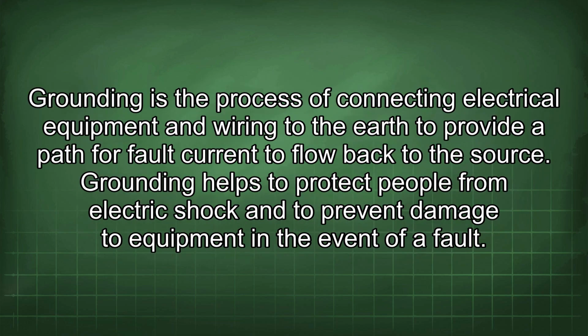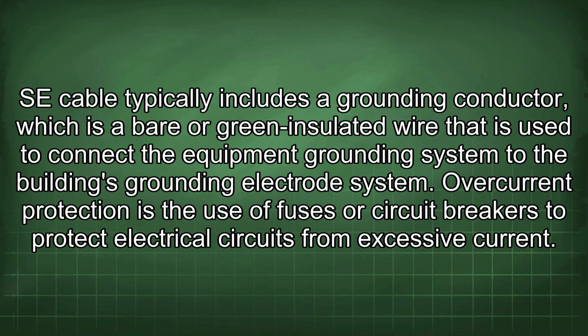Grounding is the process of connecting electrical equipment and wiring to the earth to provide a path for fault current to flow back to the source. Grounding helps to protect people from electric shock and to prevent damage to equipment in the event of a fault. SE cable typically includes a grounding conductor, which is a bare or green insulated wire that is used to connect the equipment grounding system to the building's grounding electrode system.